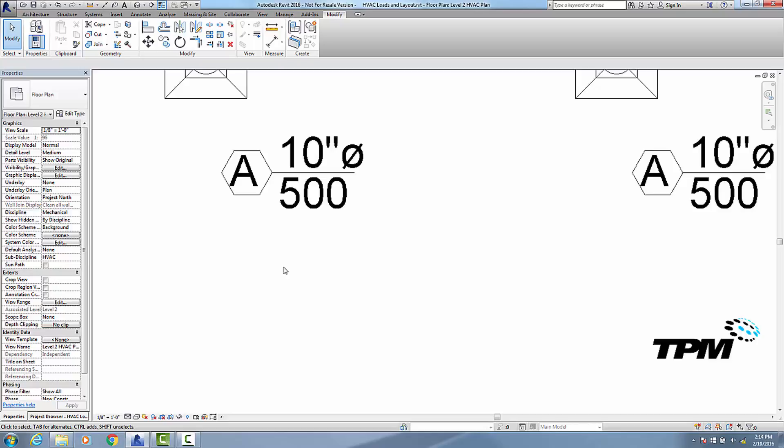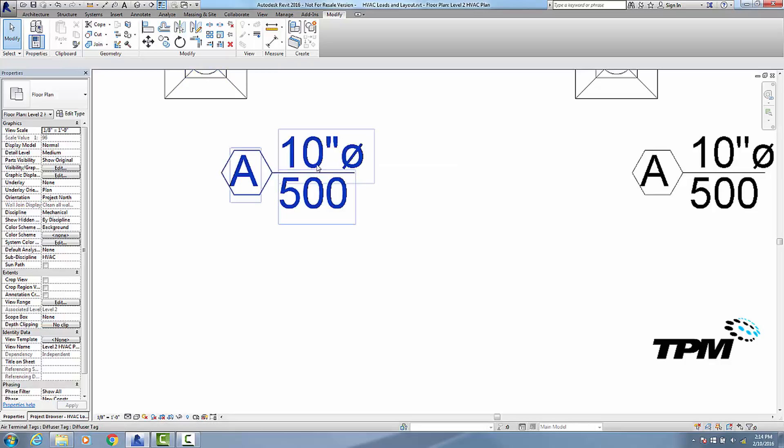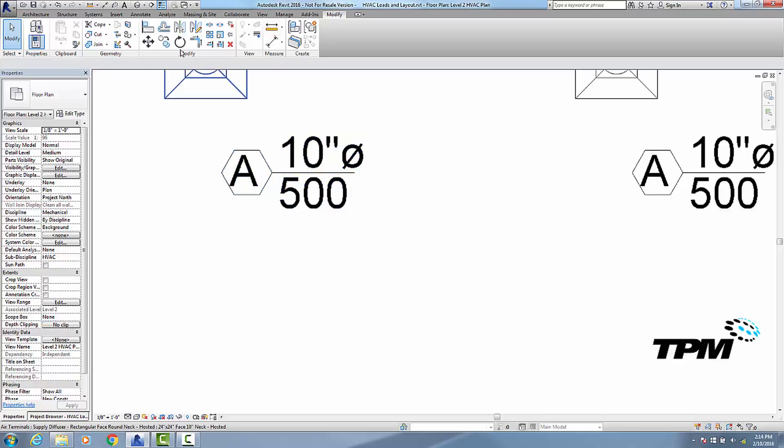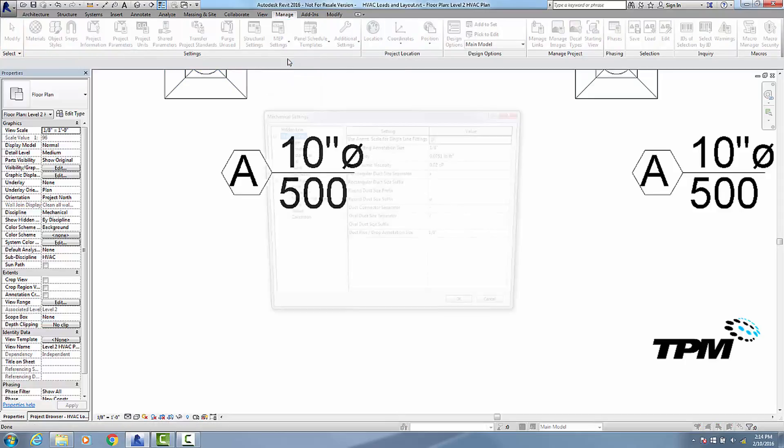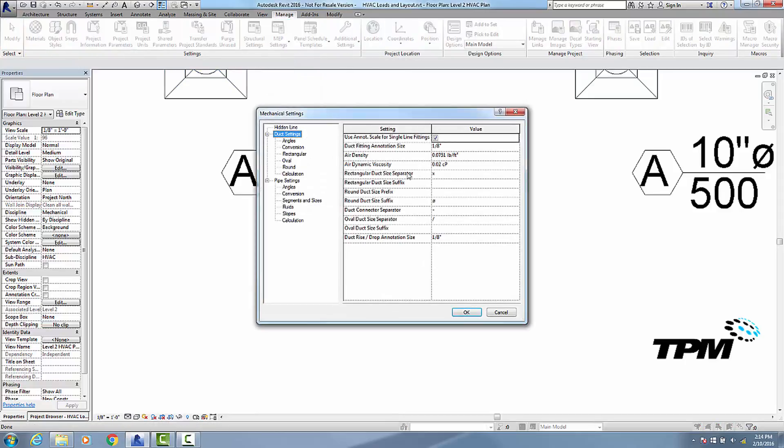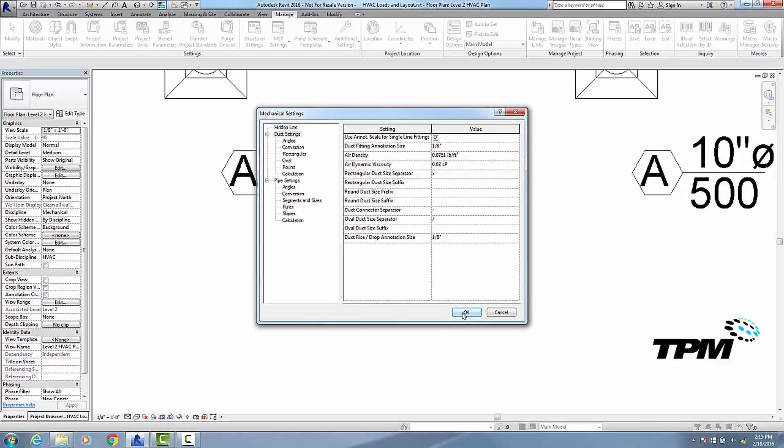So let me show you how to get rid of that diameter symbol. Now remember, it's not just this tag; it would also get rid of it anywhere, like on a duct label or something like that as well. So I'm going to go to manage, go to my MEP settings, mechanical settings, and on my duct settings here, where it says round duct size prefix, I'm going to delete my diameter symbol.